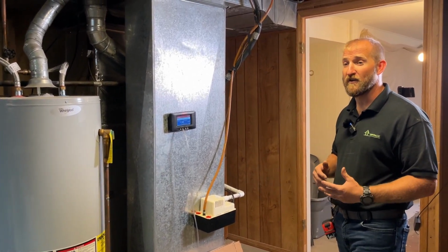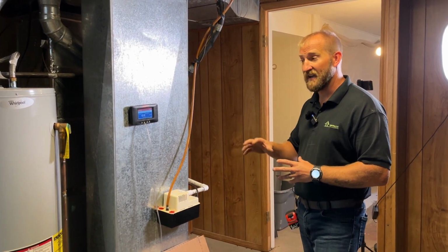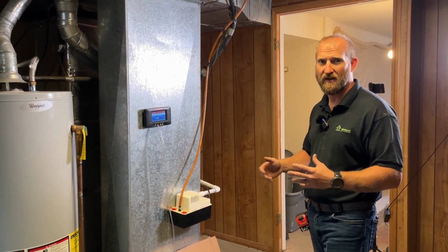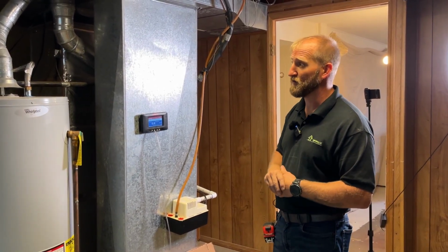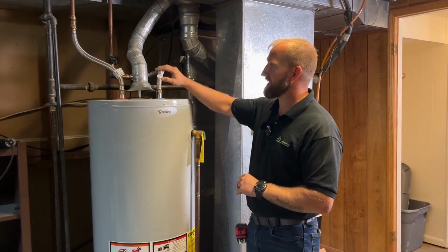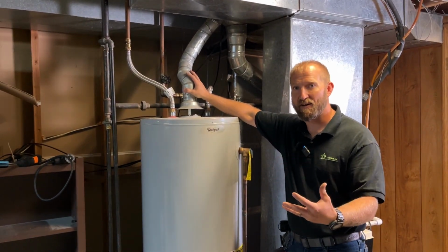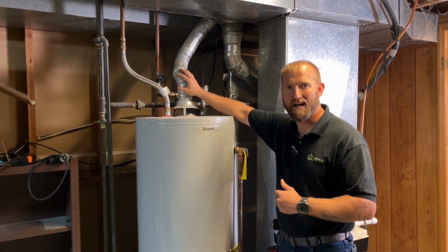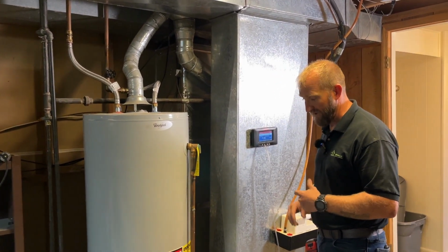If you don't have a furnace that can run independently, if the fan can't run independently from the furnace, you can skip that step according to BPI, because you don't want to run the furnace and get a hot flue pipe. So one of the things that we're going to do before we start our water heater is identify if it's a hot flue or a cold flue. If it hasn't been running because we've had it off this whole time, it should be a cold flue. You can feel it. It's not hot to the touch. So you've got a cold flue for our startup. That's what we want to see.